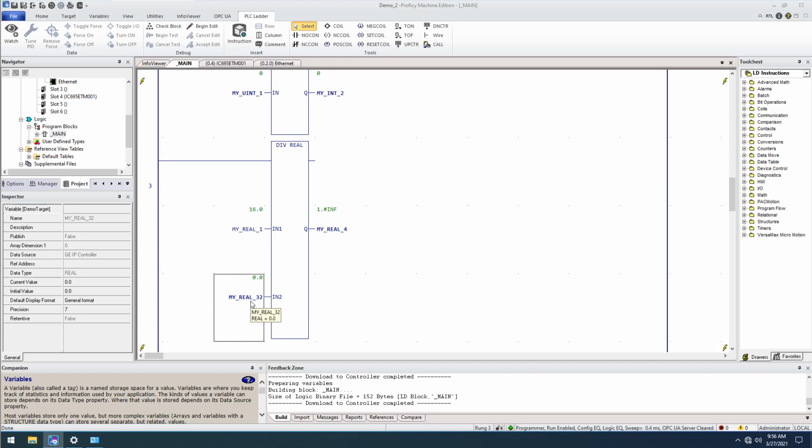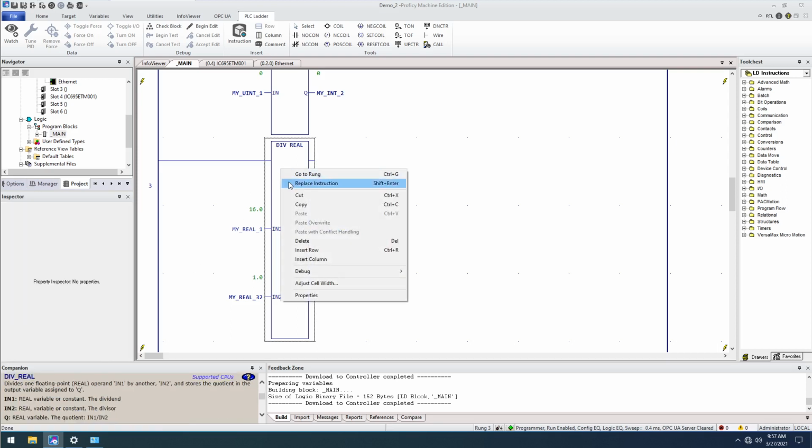So what you really should be doing is whenever you're doing any logic execution for division, always ensure that you're checking the variables that you're dividing against before you execute the division instruction, where you could do something like, as long as the denominator, the in2, is not equal to 0, then you can execute your division instruction. This is so you just don't run into unexpected errors in your logic, which could have effects on any downstream logic. So there's very simple division, and let's do multiplication.